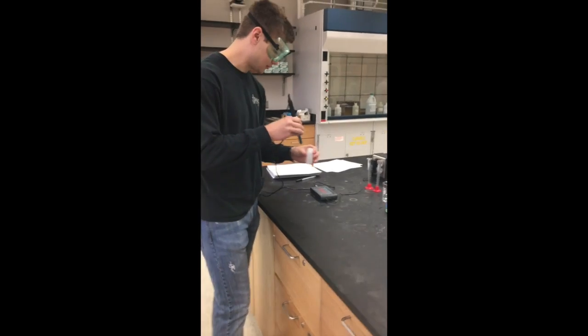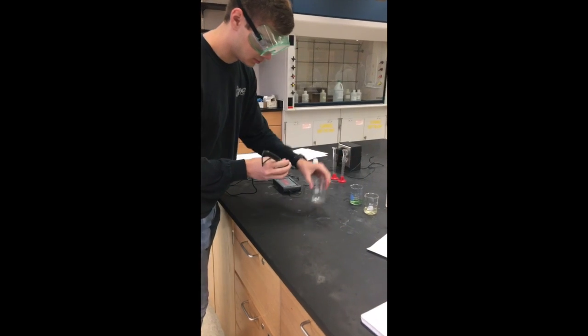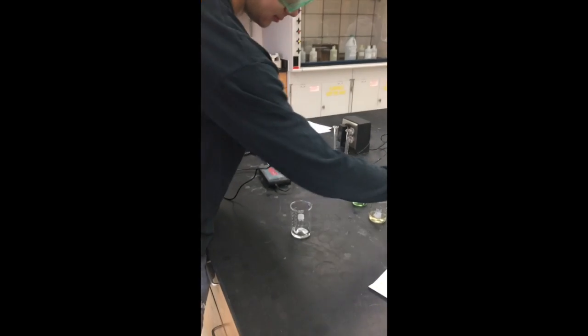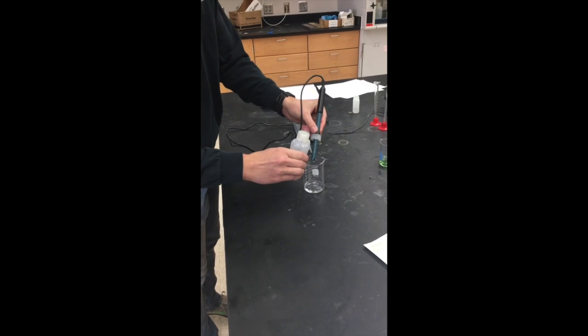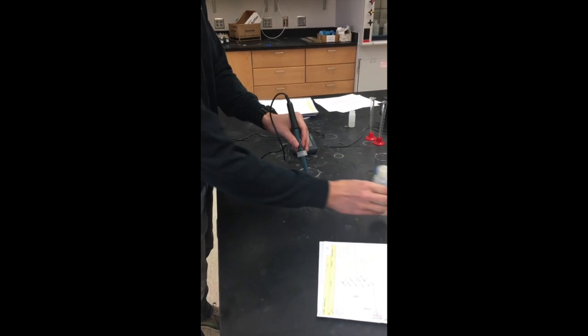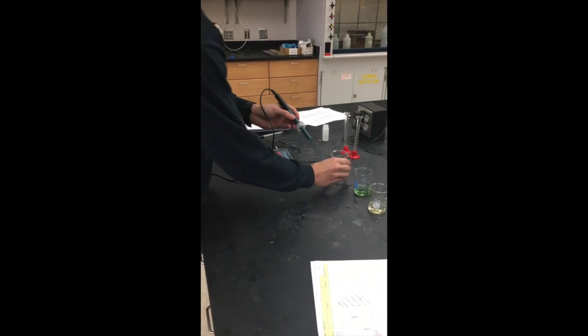First, we are going to calibrate the pH meter. After removing the probe bottle, rinse the probe with deionized water into a waste beaker. Then, put the probe into a beaker of the known pH 7 buffer solution.